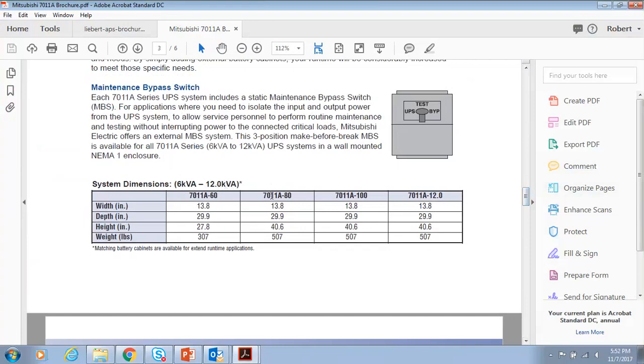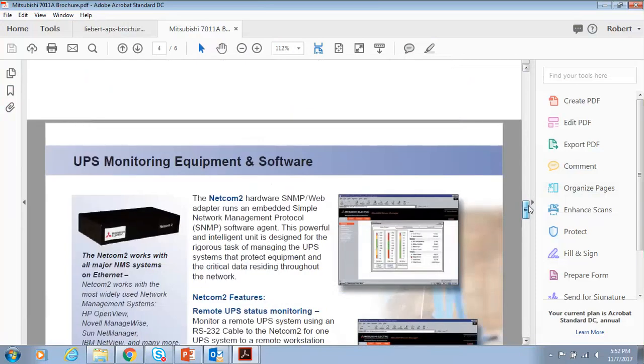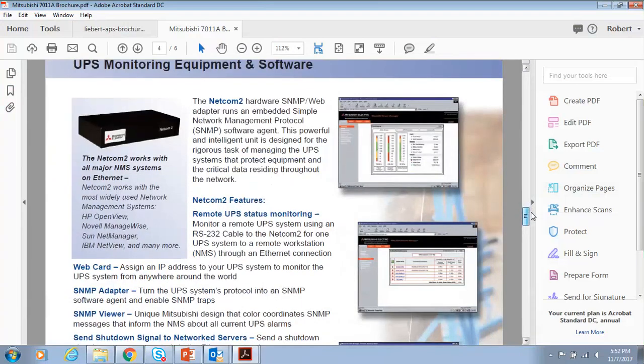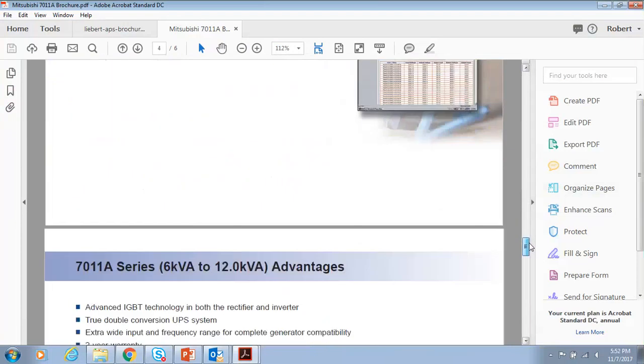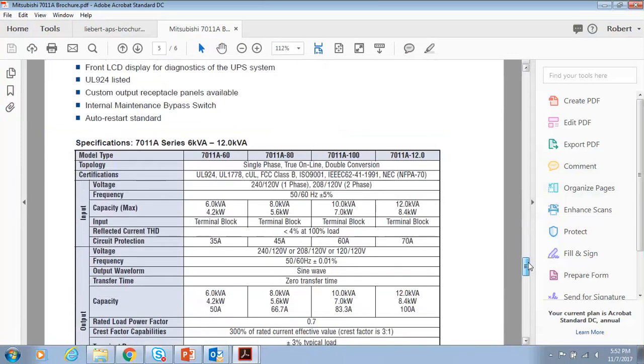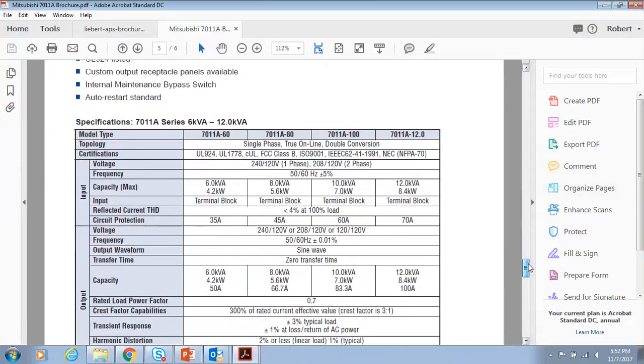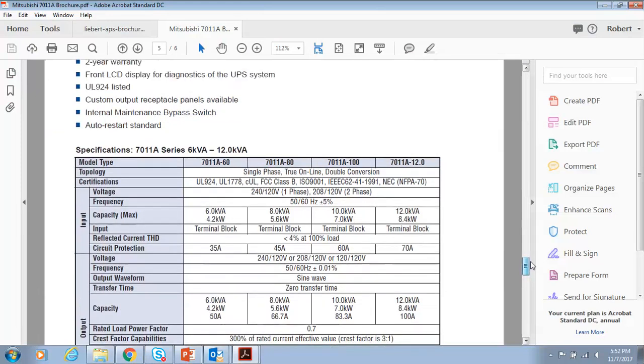So they've got a 6, 8, 10, and 12 kVA unit. You'll see similar software capabilities for graceful shutdowns and network communications, and again specifications in a similar format. Their efficiency ratings may be a little bit less than the Vertiv - on the power factor, you can see how many watts versus how many kVA are coming out of these things.